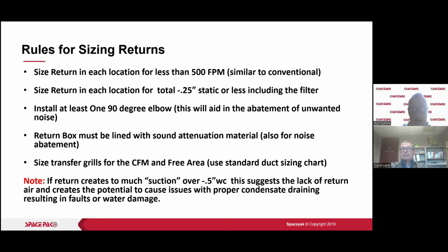All right, so sound travels in a direct line. This 90-degree helps to attenuate that sound, because now it's not traveling right to the filter grill and being heard outside. The return box must be lined with sound attenuation material or insulation if you're making your own return box, return plenum. Our return duct material, the 10-foot section, is an odd size, and not only that, it has cloth sound attenuation material, the same that you see in the sound attenuators. So that's another advantage to using our duct. You've already got sound attenuation built into that.